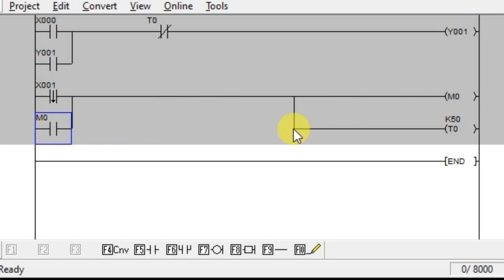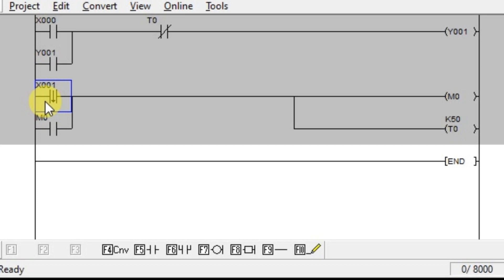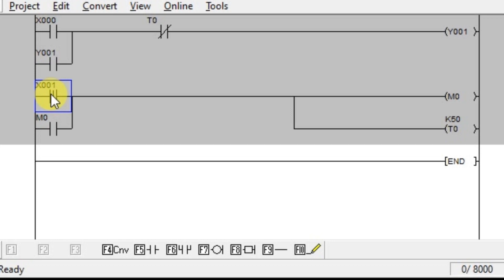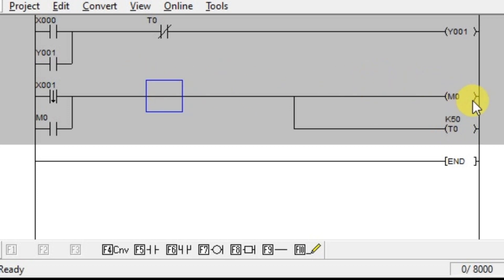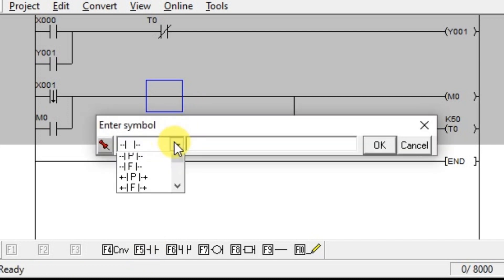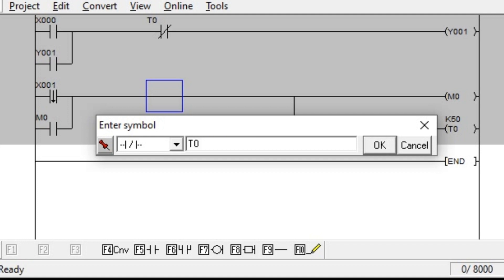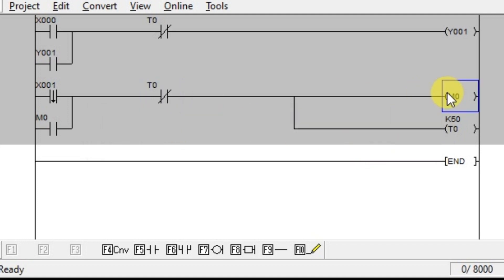We used one internal memory M0 here. For the timer, it needs a continuous input. During the 5-second running time it needs a continuous input, but we used a falling edge input instruction — this will only give you a single pulse whenever the sensor changes its state from ON to OFF. For the timer we need a continuous signal, so with the help of the exit sensor we activated an internal memory and used a latch to provide a continuous signal to the timer. After the timer completes its operation, we have to unlatch the memory bit M0 also — otherwise it cannot work a second time. If it continuously stays on, the timer is not going to run again. So insert an NC contact of timer T0 to unlatch the memory bit address.